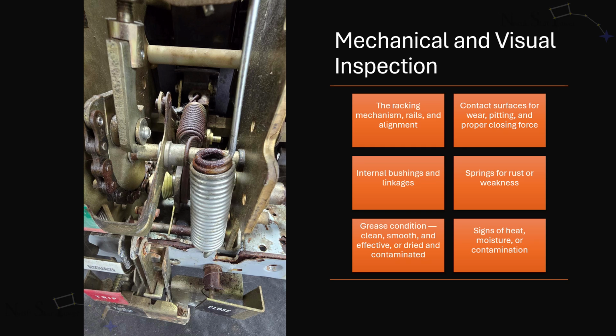During inspection, we check the racking mechanism, rails, and alignment, contact surfaces for wear, pitting, and proper closing force, internal bushings and linkages, springs for rust or weakness, grease condition, clean, smooth, and effective, or dried and contaminated, signs of heat, moisture, or contamination. Just like an engine needs oil changes, circuit breakers need to be cleaned, lubricated, and adjusted regularly to prevent failure during a critical event.